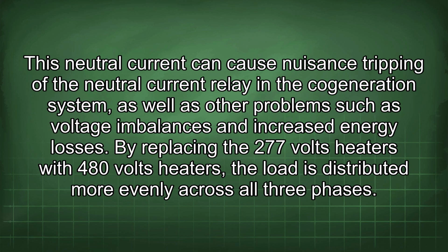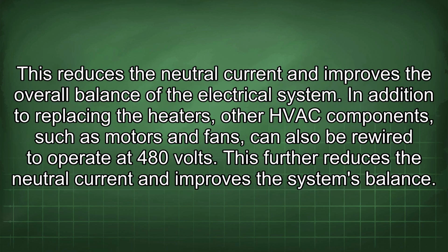This neutral current can cause nuisance tripping of the neutral current relay in the cogeneration system, as well as other problems such as voltage imbalances and increased energy losses. By replacing the 277 volt heaters with 480 volt heaters, the load is distributed more evenly across all three phases. This reduces the neutral current and improves the overall balance of the electrical system. In addition to replacing the heaters, other HVAC components such as motors and fans can also be rewired to operate at 480 volts. This further reduces the neutral current and improves the system's balance.